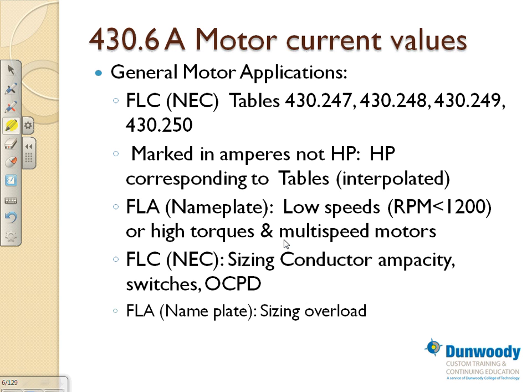Interpolated. I don't know how many of you guys have done interpolation. When you have a number between two numbers corresponding to another two numbers, and there's one number between these two, I can find the other number. I don't want to go there, but the way I always encourage people, if you know the amp of that motor, just go to the next horsepower. If it's 90 and there's no 90, go to 100 and they'll give you the horsepower for that one.